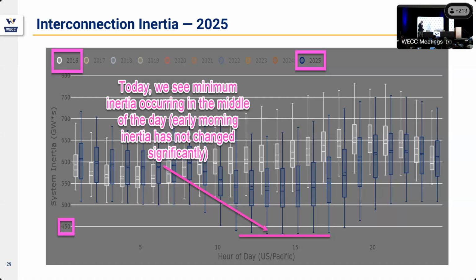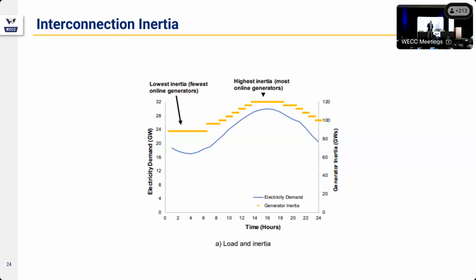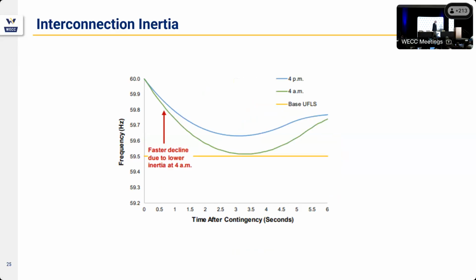One of the things we're seeing in the West is what we call time to nadir. Anytime we have a frequency deviation, let me go back to here. The nadir is the bottom of the curve. That's the most important point, because we always want to stay out of underfrequency load shedding. In the West, historically before IBRs, we normally hit the nadir in about 8 to 10 seconds, which means frequency decline is not instantaneous; it drops over about a 10-second time frame. As all that inertial energy is given up, we start plateauing out at the bottom, and then the governors are injecting megawatts, and we recover the frequency back up to deadband.